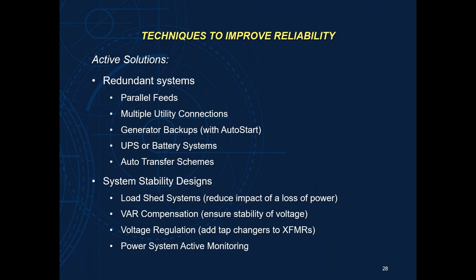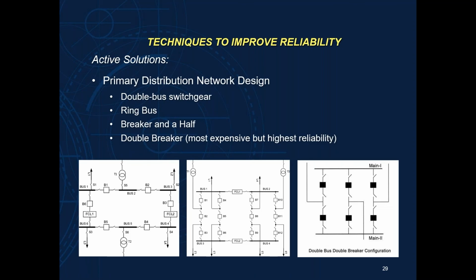Stability designs, load shedding systems, so that instead of taking a total loss, we can take only a partial loss. That's going to improve our bottom line at the end of the year. Voltage regulation, making sure our voltage is efficient and that we're not going to suffer a dropout of load because of a little fluctuation in voltage somewhere. All of this will help our system out. We can look at our primary distribution design. These are just some different ideas that are out there and that are used today.